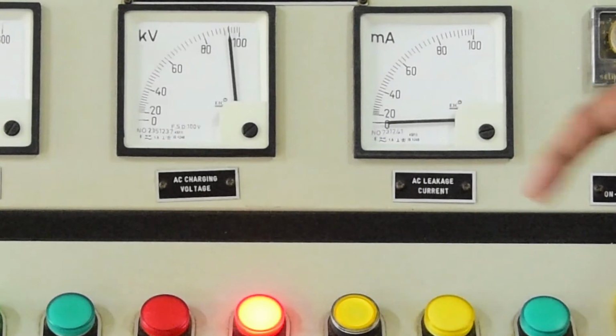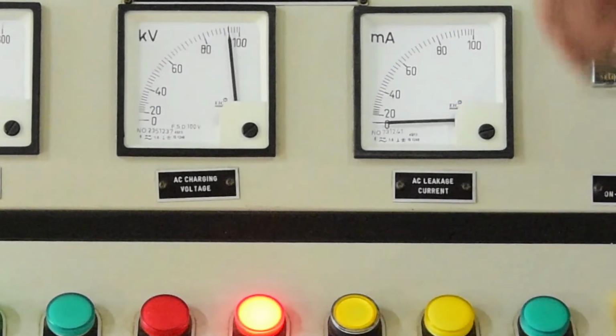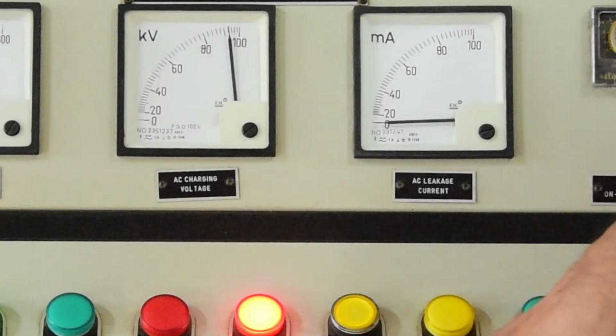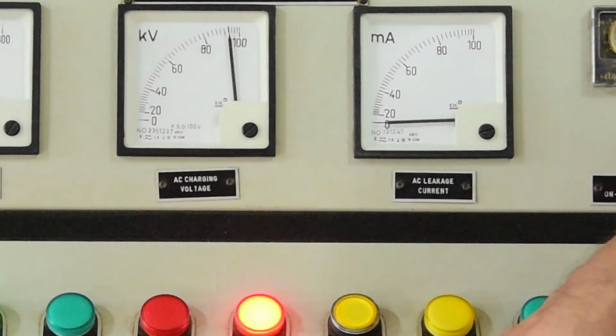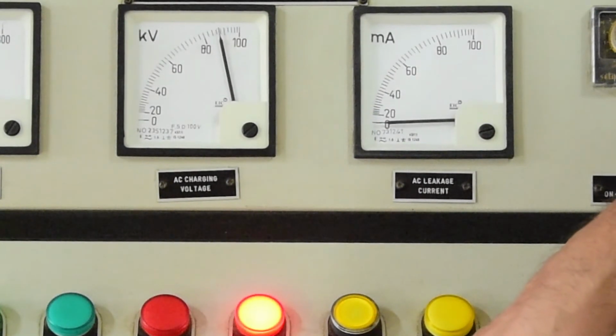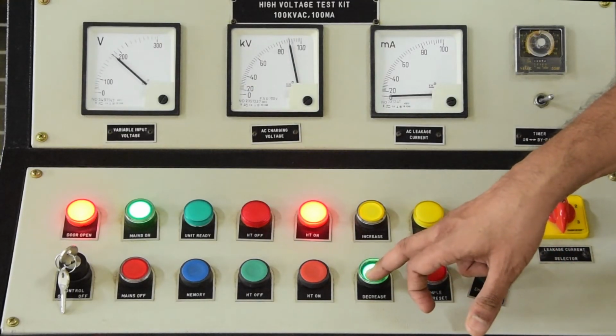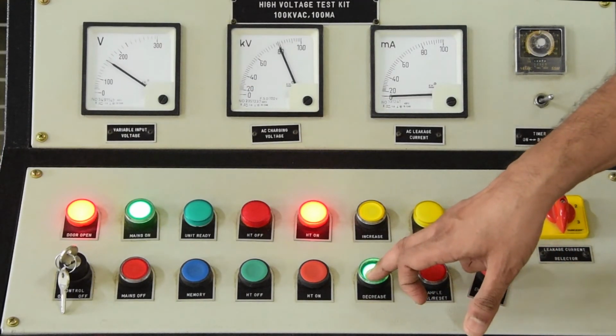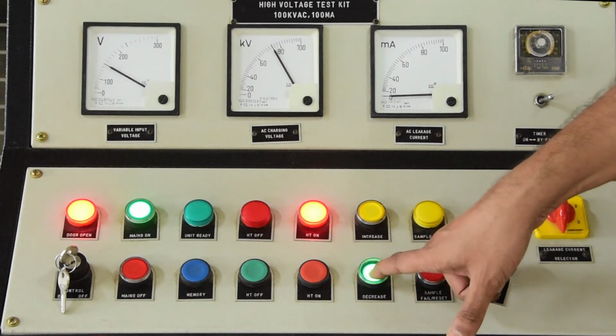Here, as we have reached a potential of nearly 92 kV, there is a noise heard in the video. You can clearly see that the sphere gap has been ionized and current is flowing to the ground through the high resistance. So the 1 centimeter, or 10 millimeter, gap has failed at a potential of 92 kV.